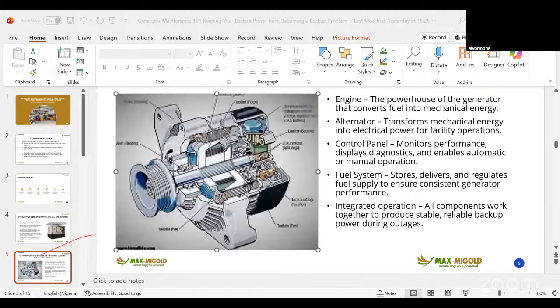Maybe you have like 3 ACs in each of the flats. So you have 3 ACs, 2 water heaters, and thereabouts. Determine the wattage of those equipment and multiply it by the number of apartment units that you have. Then you have the aggregate power demand as built. After getting it, you determine the kVA. Maybe the total load you arrive at is about 1,000 kilowatts. Divide that 1,000 by 0.8, that's the power factor, to determine the exact kVA that will power that building.